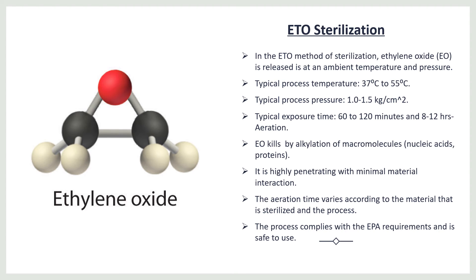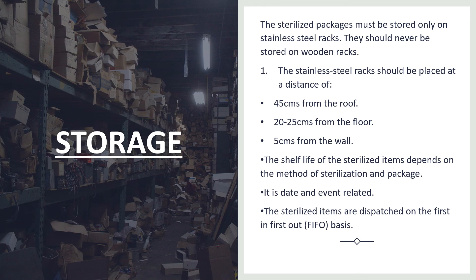ETO — ethylene oxide — is released at ambient temperature and pressure. The typical process temperature is 37 to 55 degrees Celsius, typical process pressure is 1 to 1.5 kg per centimeter square, and exposure time is typically 60 to 120 minutes. ETO kills microorganisms by alkylation of macromolecules. It is highly penetrating with minimal material interaction. The aeration time varies according to the material being sterilized, and the process must comply with EPA requirements.